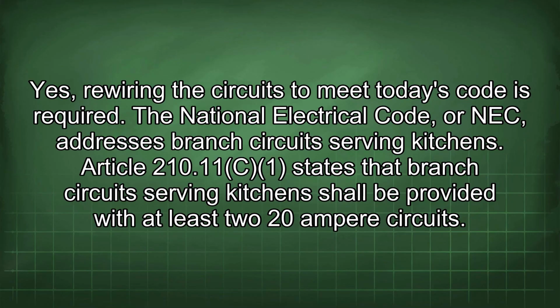Yes, rewiring the circuits to meet today's code is required. The National Electrical Code, or NEC, addresses branch circuits serving kitchens. Article 210.11 states that branch circuits serving kitchens shall be provided with at least two 20-ampere circuits.